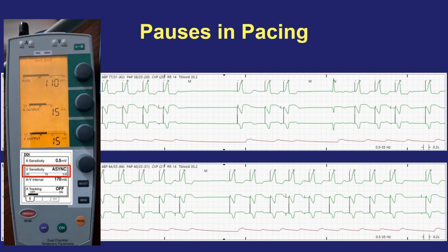Although a caveat, as we'll review in a short bit, sometimes you don't want the pacemaker to just pace no matter what. You want it to inhibit if there are real ventricular events happening, because you don't want the pacemaker to pace on top of T waves, which occasionally can actually lead to proarrhythmia, as we will review. So the async setting has a hazard that you may have inappropriate pacing output at the wrong time. So it's often best to find a sensitivity number where it is appropriately inhibiting when QRSs are occurring, but there isn't inhibition of pacing during periods of silence due to other smaller electrical noise in the room or in the patient's body.